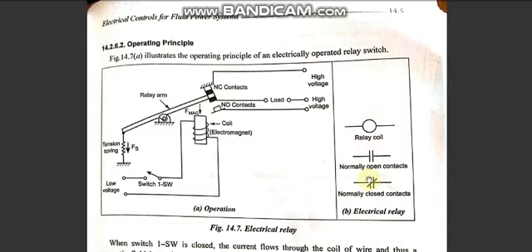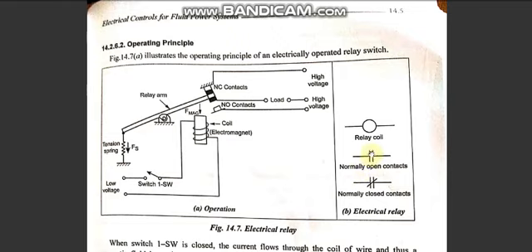CR is the symbol for a relay coil. A normally open contact means the contact is open by default. A normally closed contact means both contacts are in a closed condition. When you energize the electromagnetic coil, it pulls the arm and the normally open contact closes. For a normally closed contact, energizing the coil causes it to open.